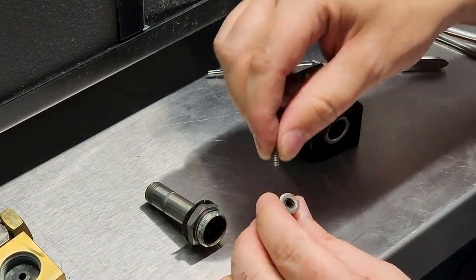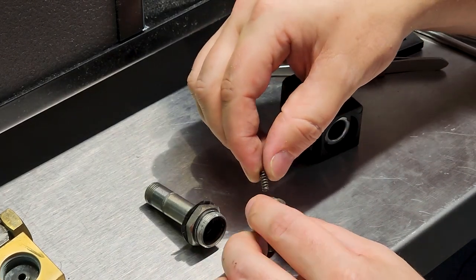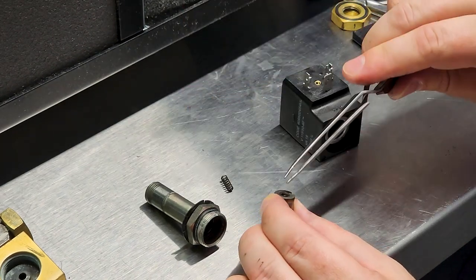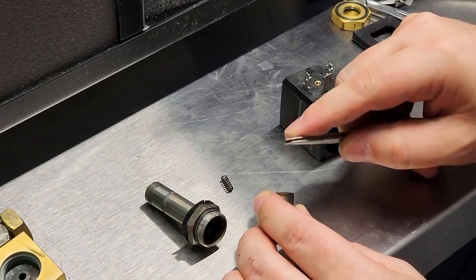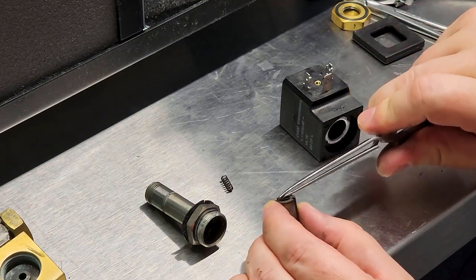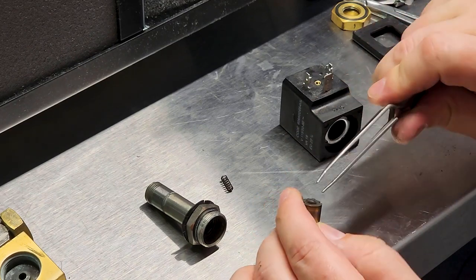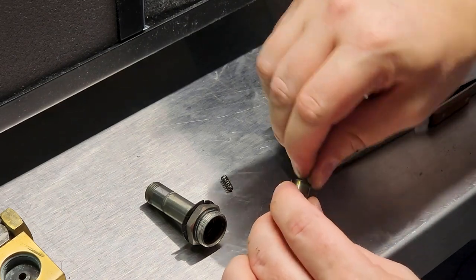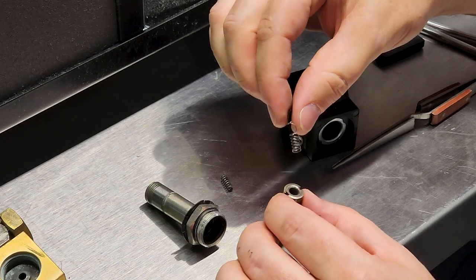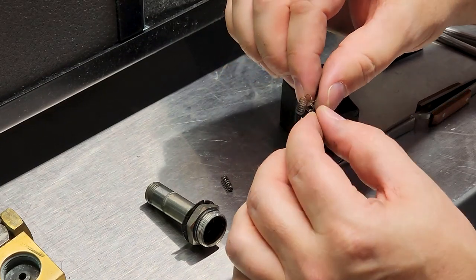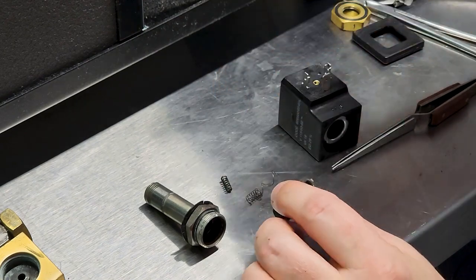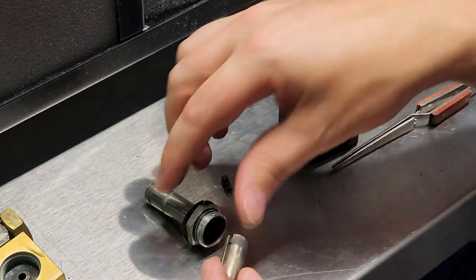Now if you see, the spring was not easy to pull out. That was absolute garbage, and I believe that there's so much soot and garbage inside this. Oh geez, sorry guys, there we go. Oh my goodness. There's a broken coil right there. There's all sorts of garbage down in there. So this right here is your piston.